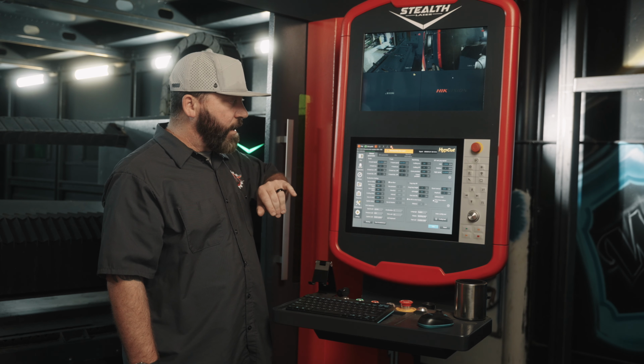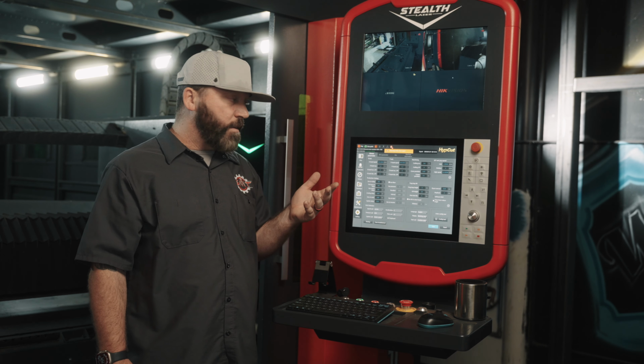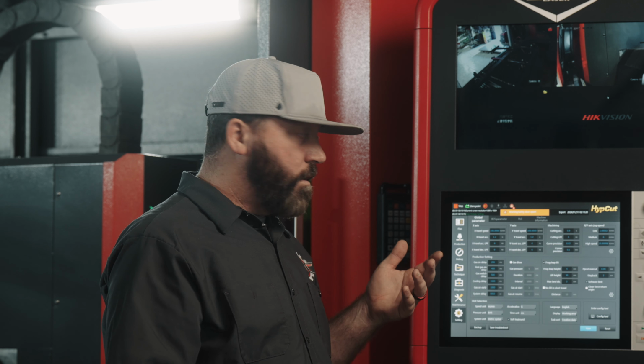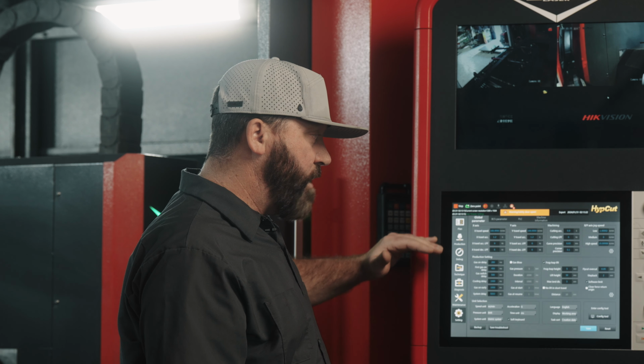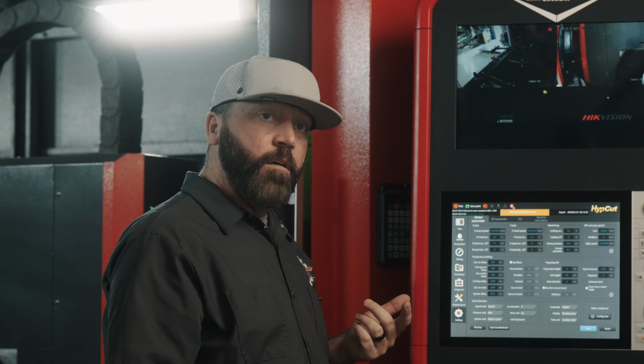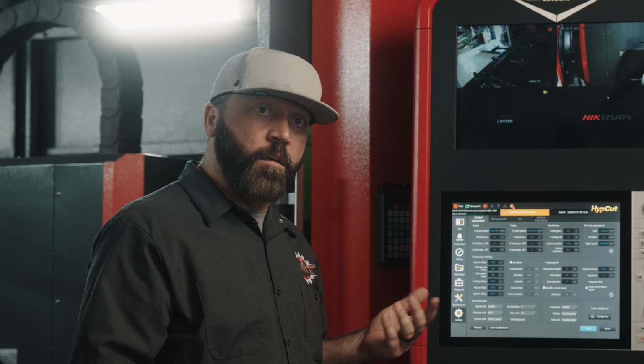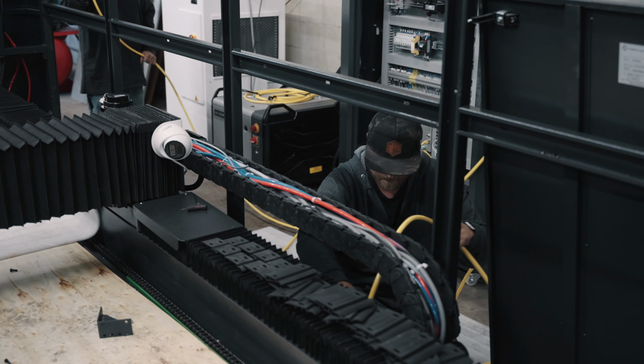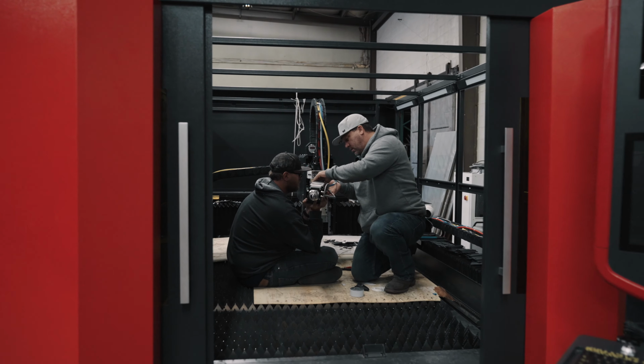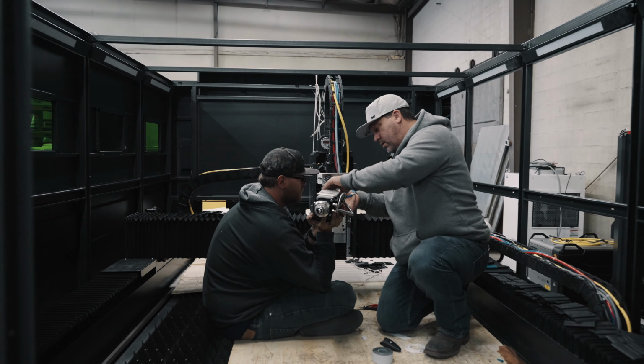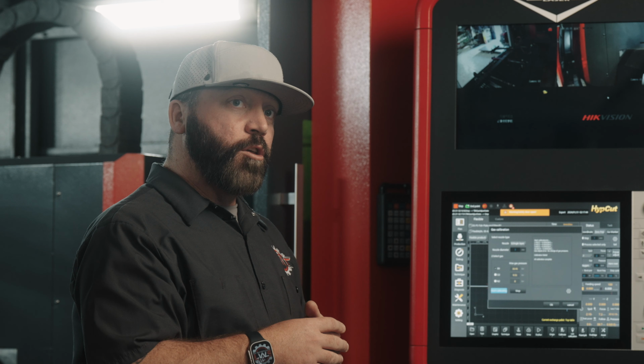We have a settings parameter, which allows you to increase and decrease feeds and speeds. This machine is set up to run at a specific speed for our material and our daily materials that we throw at it. Historically, on another system, if you don't have the ability to calibrate like that and use a good high quality proportioning valve, you just don't know.